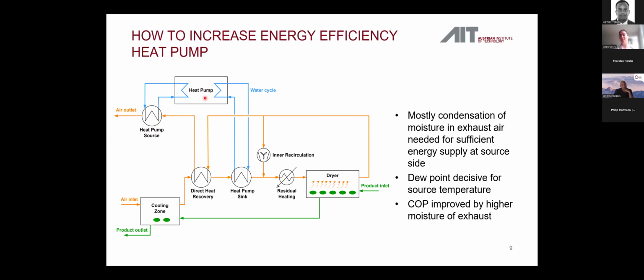In this case, the heat pump is implemented using water cycles, as well on the sink side as on the source side, to provide enough energy for the heat pump to run the whole drying process. Usually, condensation on the source side of the heat pump is needed, so that the exhaust air temperature needs to be cooled down below the dew point. In this case, the dew point is then decisive for the source temperature and so has a large influence on the COP of the heat pump.